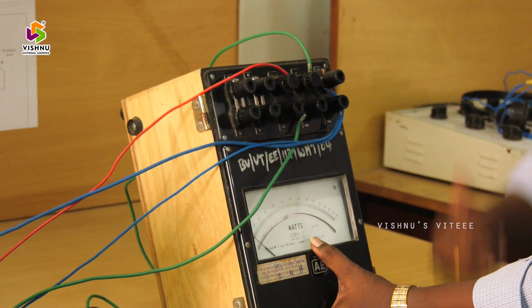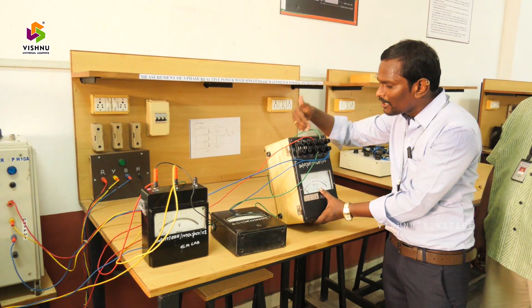In star connected load phase current is equal to line current. So here fixed coils measure line current. IR equals IL, so we are taking IL. Fixed coils measure line current IL. Similarly pressure coils connected in between B and Y phase measure line voltage. So line current into line voltage, and it measures phase angle between, this point is very important, it measures phase angle between IR and VBY.